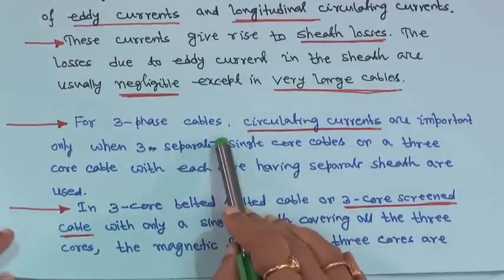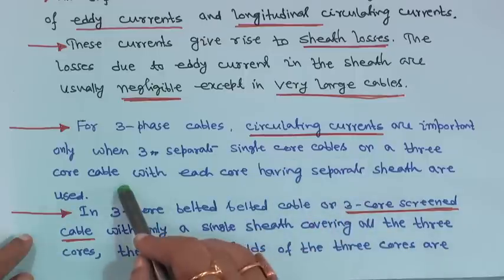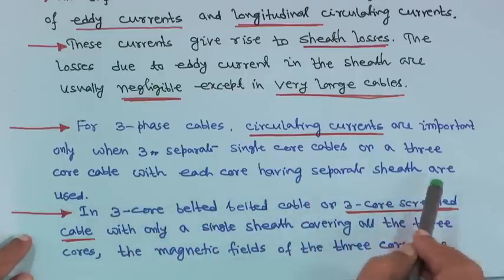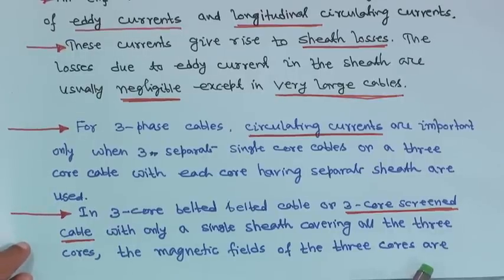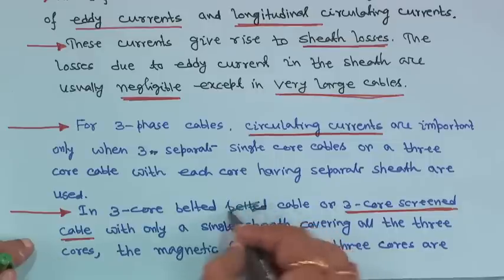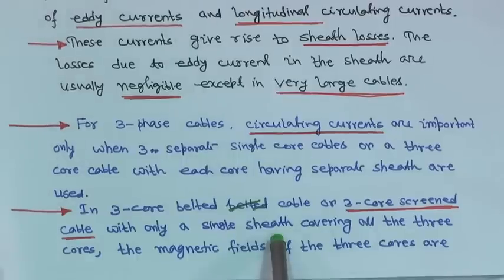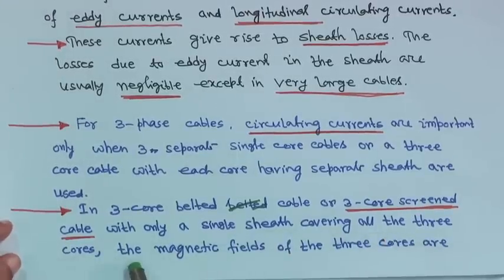For 3-phase cables, circulating currents are important only when 3 separate single core cables or a 3-core cable with each core having a separate sheath are used. In 3-core belted cables or a 3-core screened cable with only a single sheath covering all 3 cores, the magnetic fields of the 3 cores are partially mutually compensated and the circulating currents are reduced.